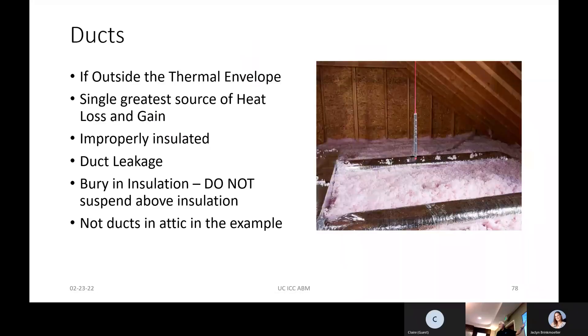If the house was planning on mechanical ventilation, we should put it there. I see people put in a whole bunch of ventilation air to make the system bigger, but you look at the duct system or the house plan and there's no indication of a ventilation system. We're just trying to anticipate and understand how the envelope's being built. Any questions? We could go through every room in the house and verify it — don't do that. Pick a room and take a look at it.